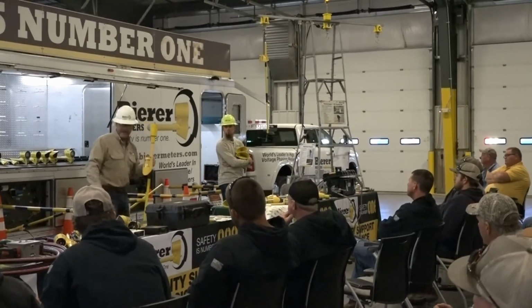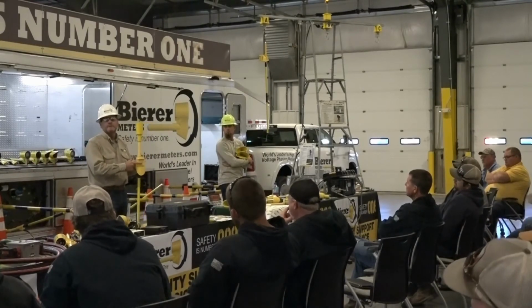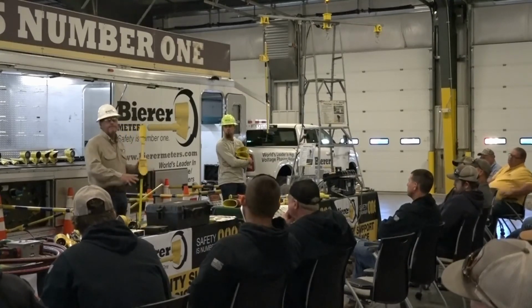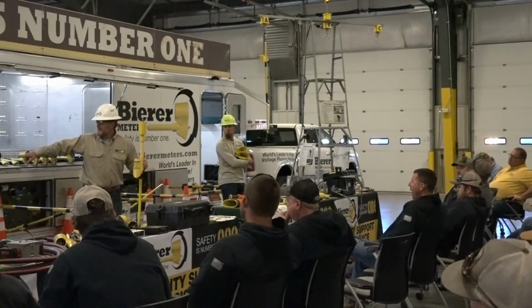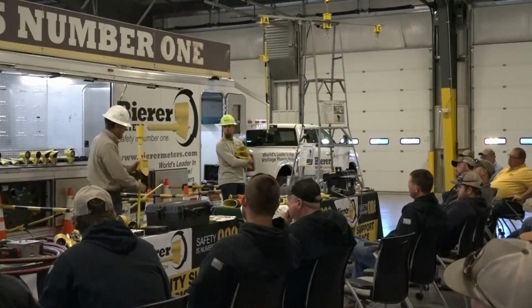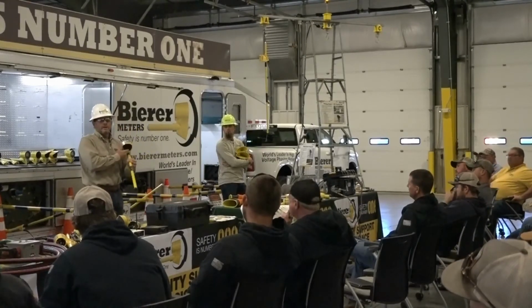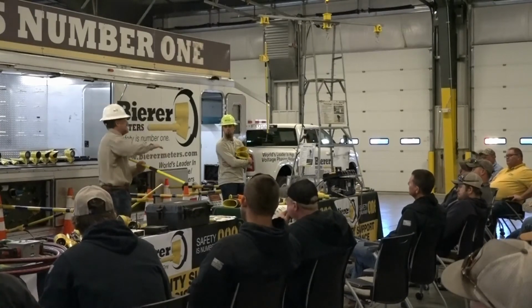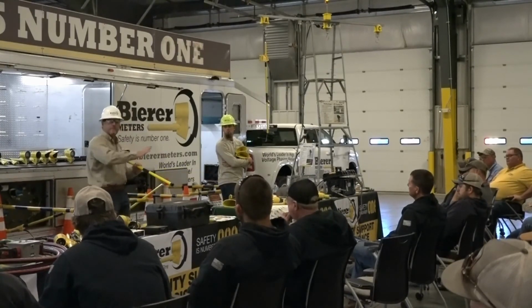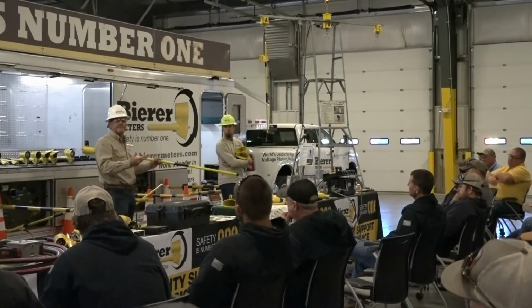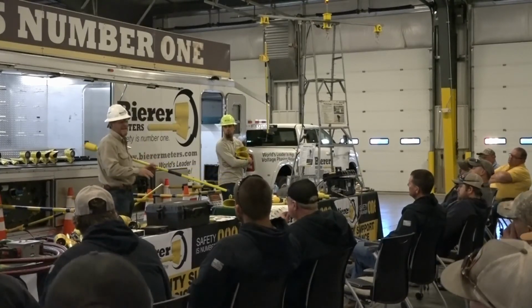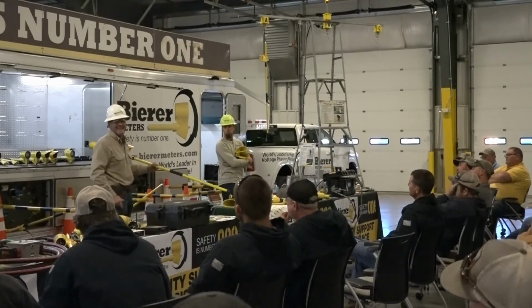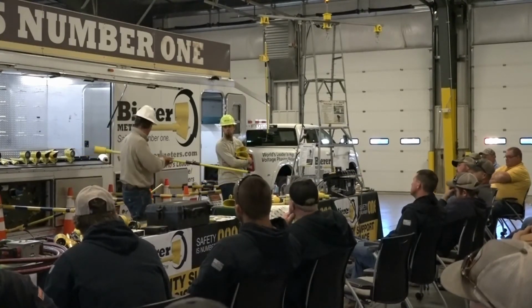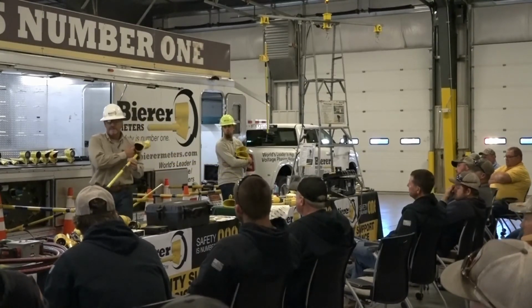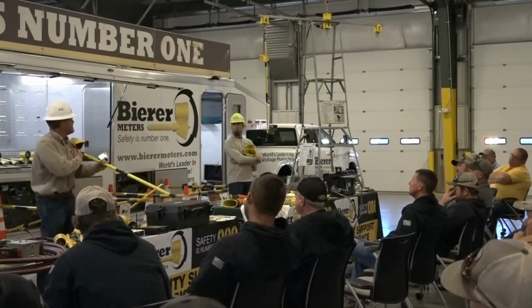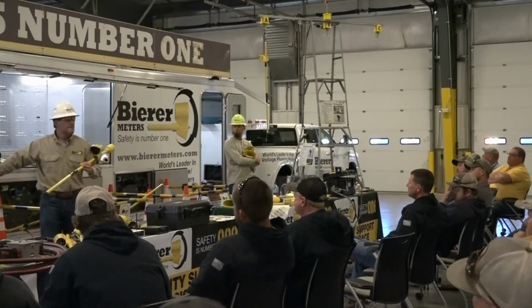So if Dylan comes over here and touches the capacitive test points, and it starts working at 50 volts, it goes up to 800 kV, secondary, primary, everything. If he touches the capacitive test points on those elbows and sees a white light close to 0, the tool is reading the phase angle, not voltage. It's not looking at potential. If it sees the same phase angle, it'll be close to zero, depending on leading and lagging power factors in the field. In this case, the generator isn't very accurate, it's bouncing back 60 hertz, so the tool doesn't like it, but it'll work fine for this presentation. If he sees zeros, or close to 0, and a white light as confirmation, he knows, since the reference is on A phase, that these elbows are A phase.